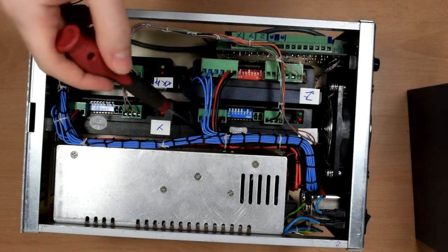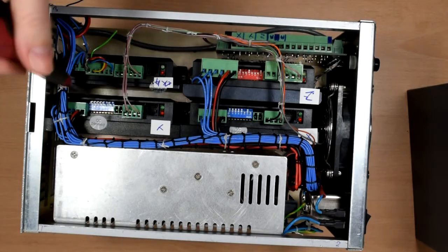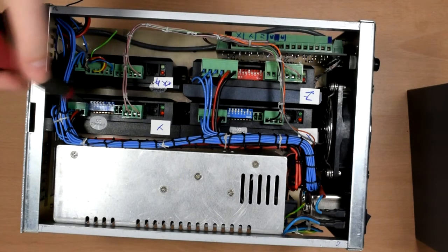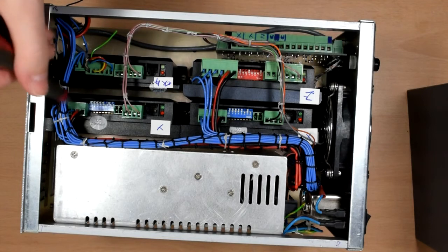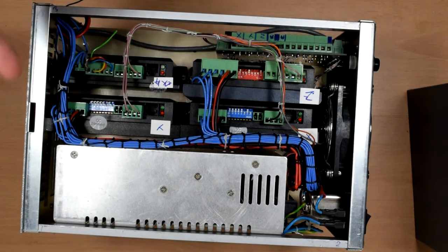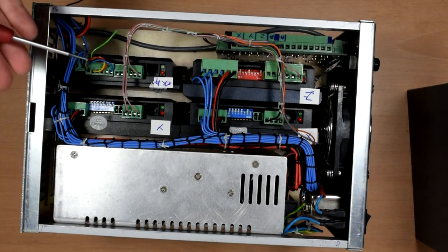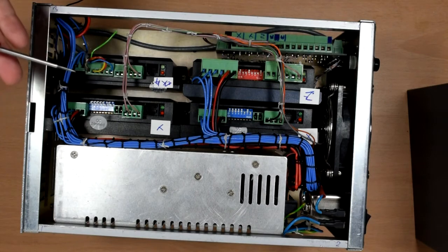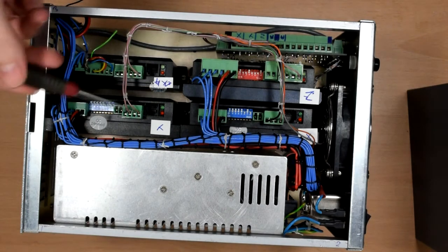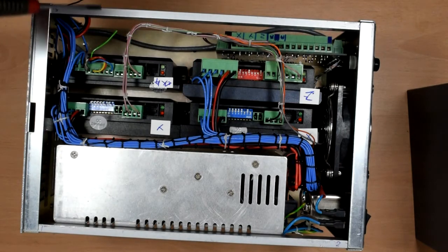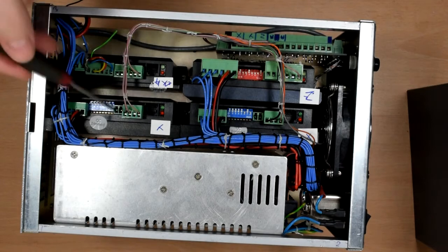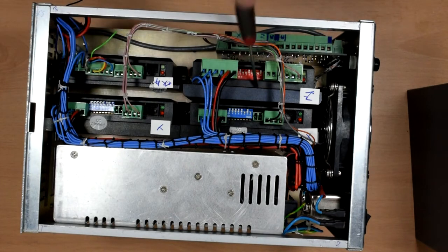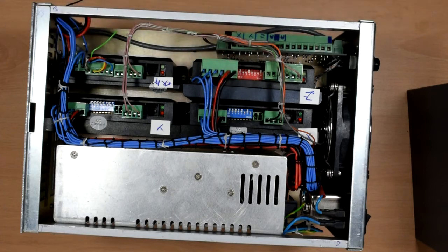These two stepper drivers are also LeadShine. Fortunately however, they have an auto-tune function that doesn't require software. You just flip one of these dip switches a couple of times and it will actually auto-tune and do a fairly good job of auto-tuning itself to a stepper motor. But of course there's no feedback from the stepper motors. It is basing everything on current draw and reverse EMF and things, but yeah they do a fair enough job actually. I don't really have any complaints with them, and this driver is actually not LeadShine, it's some UK company, and it's fine.